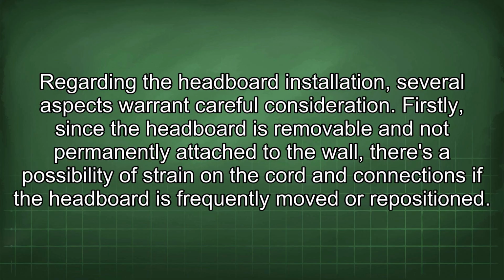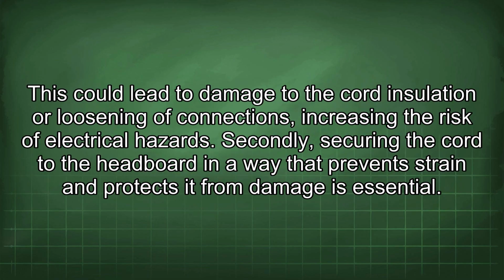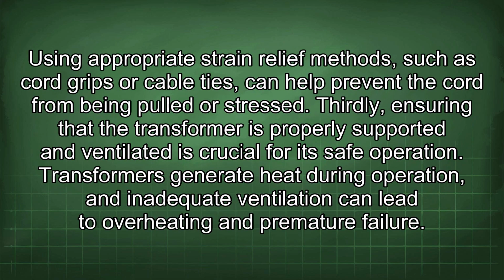Regarding the headboard installation, several aspects warrant careful consideration. Firstly, since the headboard is removable and not permanently attached to the wall, there is a possibility of strain on the cord and connections if the headboard is frequently moved or repositioned. This could lead to damage to the cord insulation or loosening of connections, increasing the risk of electrical hazards. Secondly, securing the cord to the headboard in a way that prevents strain and protects it from damage is essential. Using appropriate strain relief methods, such as cord grips or cable ties, can help prevent the cord from being pulled or stressed. Thirdly, ensuring that the transformer is properly supported and ventilated is crucial for its safe operation.